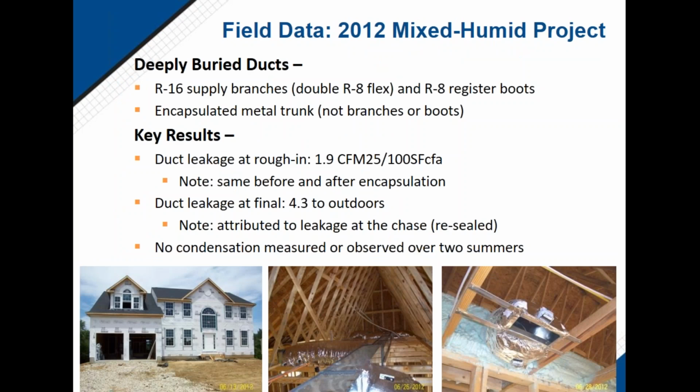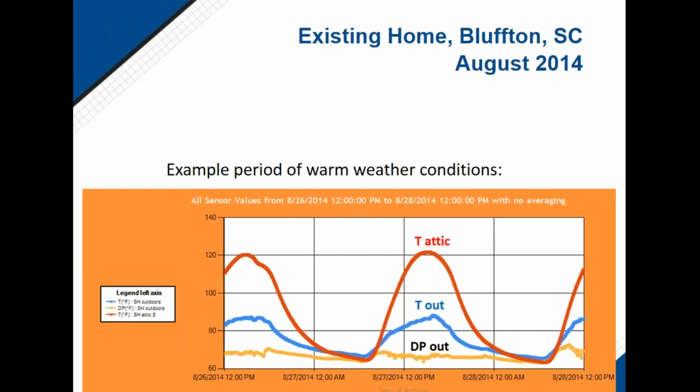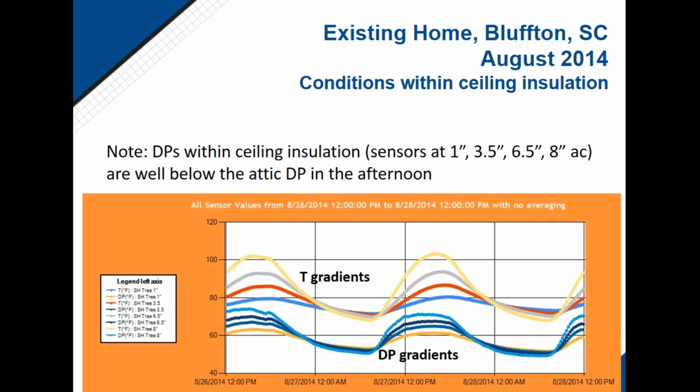You bring up that moisture question, and Leslie had a question about this. Is there a concern with condensation over time in a real-life situation where there are various people in the attic, AC service, or maybe you're working on a ceiling fan or speaker installs? Your attic typically isn't a crowded, high-traffic area, but in the construction phase, it certainly could be. Is there a concern with any of that in the early part of construction? Well, yeah, I think there is a concern. I think that's one reason why ducts sometimes get hung high in an attic, in my opinion sometimes too close to the roof deck, because it does keep them out of the way during construction. Most rough-ins occur before drywall, and ceiling insulation isn't put in until drywall. So that's a good concern.